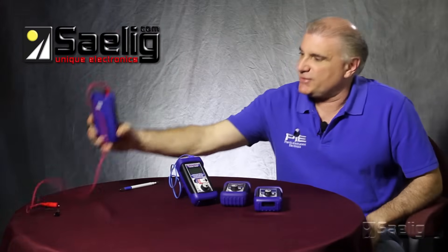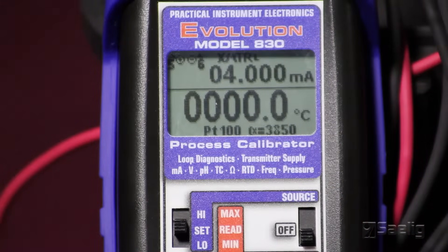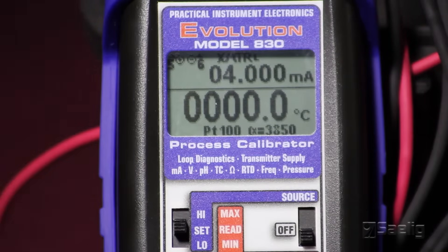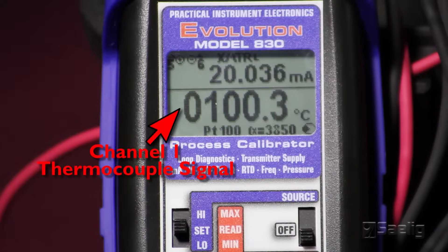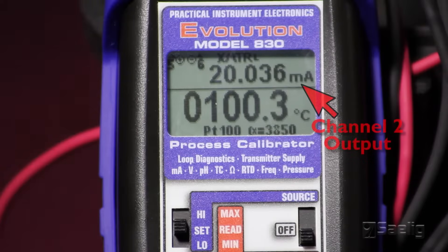The fifth calibrator in this series is the PIE 830. The PIE 830 has all the same functions and features as the 820 Elite and the 850. However, it's a two-channel calibrator. The benefit of having a two-channel calibrator is you have less equipment needed for a calibration — you can set channel 1 to source a thermocouple signal into a thermocouple transmitter and then look at the output of the transmitter on channel 2 to see if it's driving the correct 4 to 20 milliamp signal.